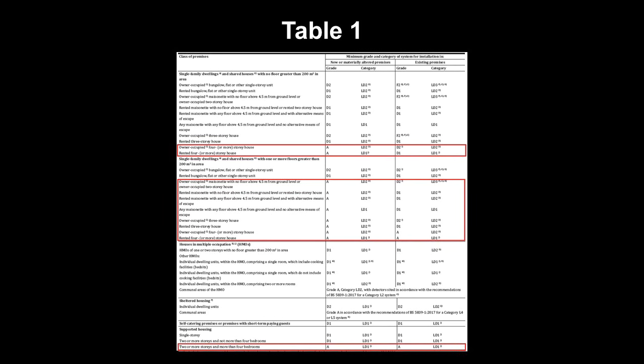But what we do is, when we're looking at what type of system in any domestic premises, and Stuart's obviously on about, you might have a 4-storey or 3-storey really large building, because that's something him and I have spoken about before. Now what you do is you go to Table 1 in the British Standards. Get the British Standards, guys. Table 1 outlines exactly what grade is recommended, what category, and that's for whether it's an existing premises or a new or materially altered building, such as a full refurb, or if you're going through building regulations.